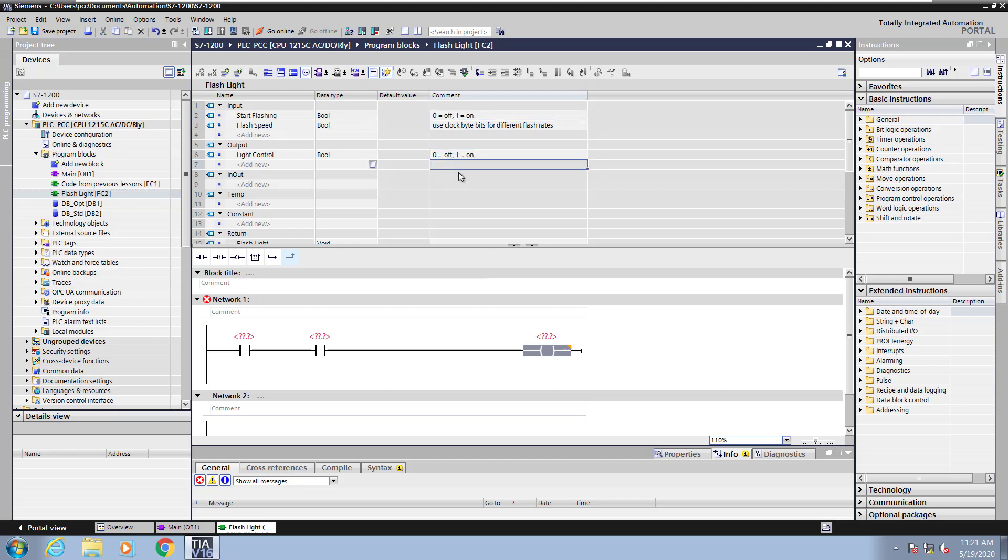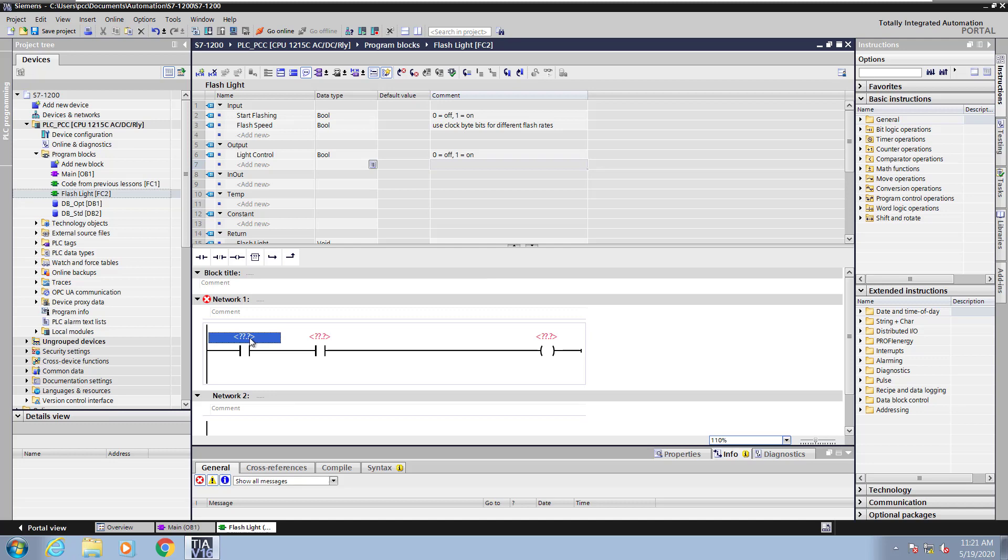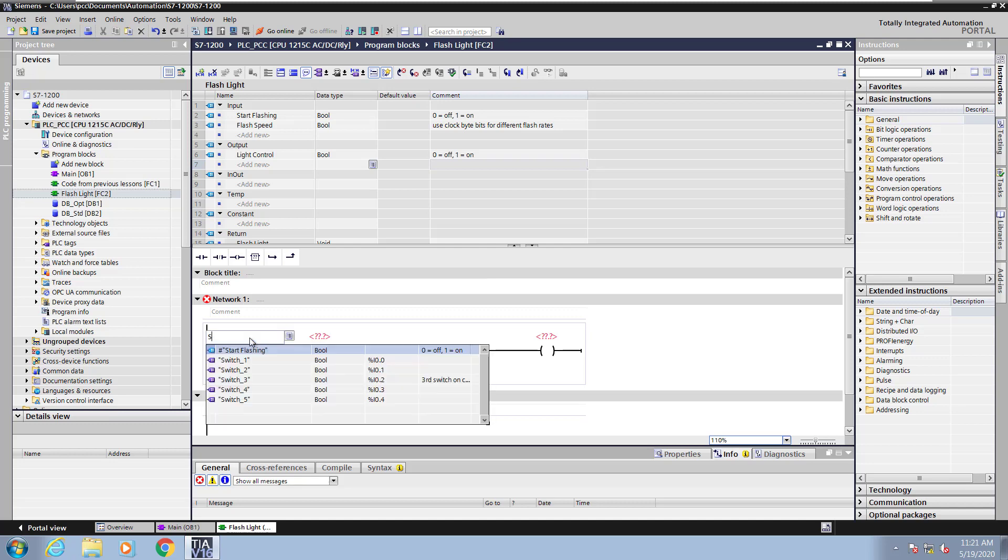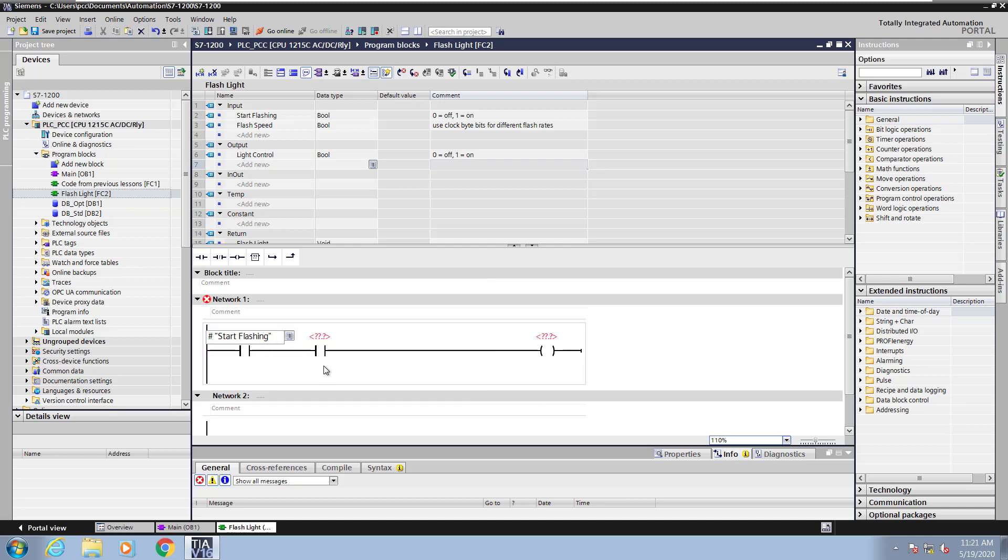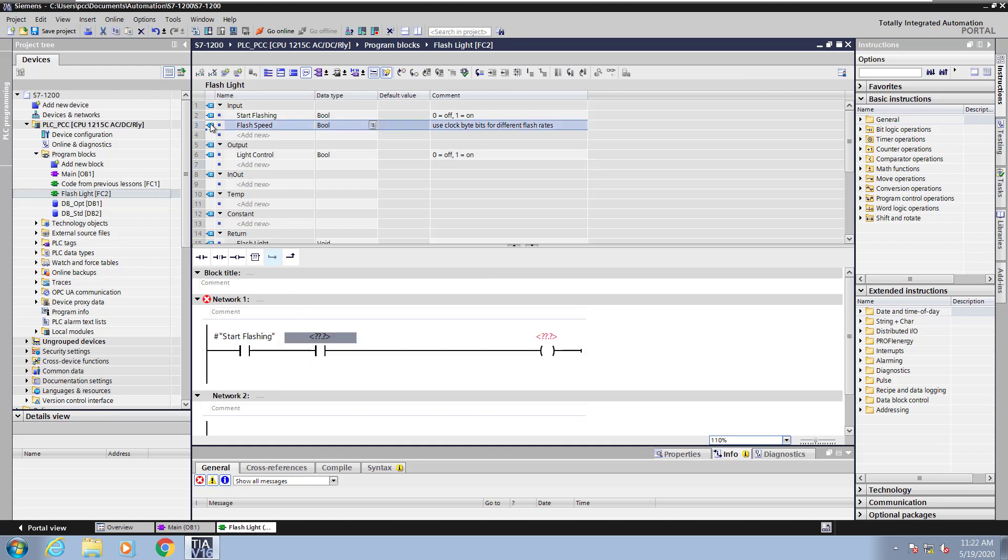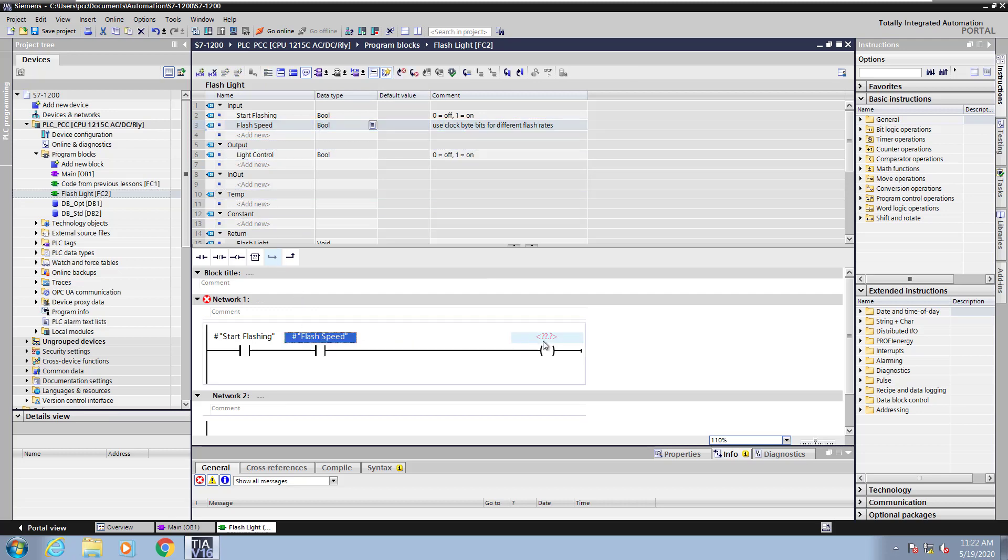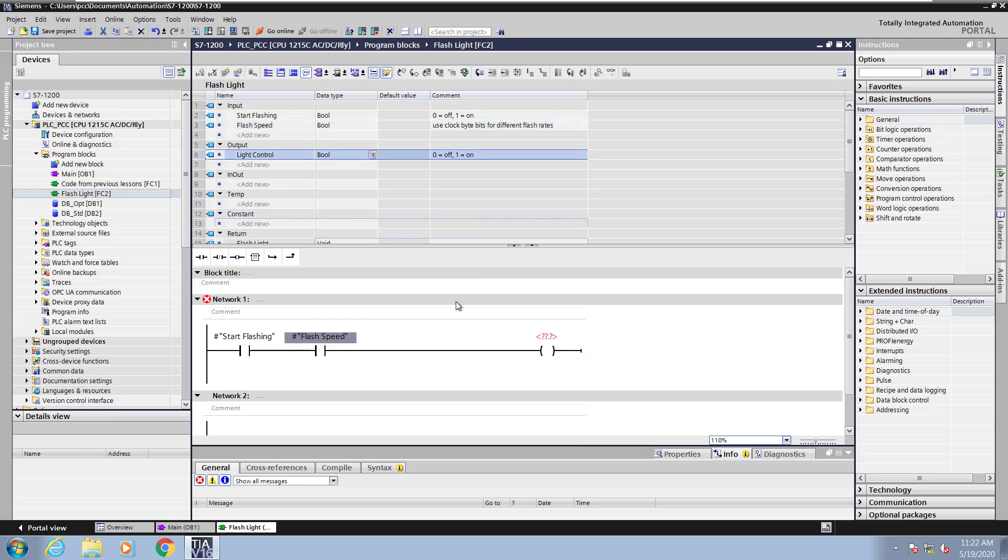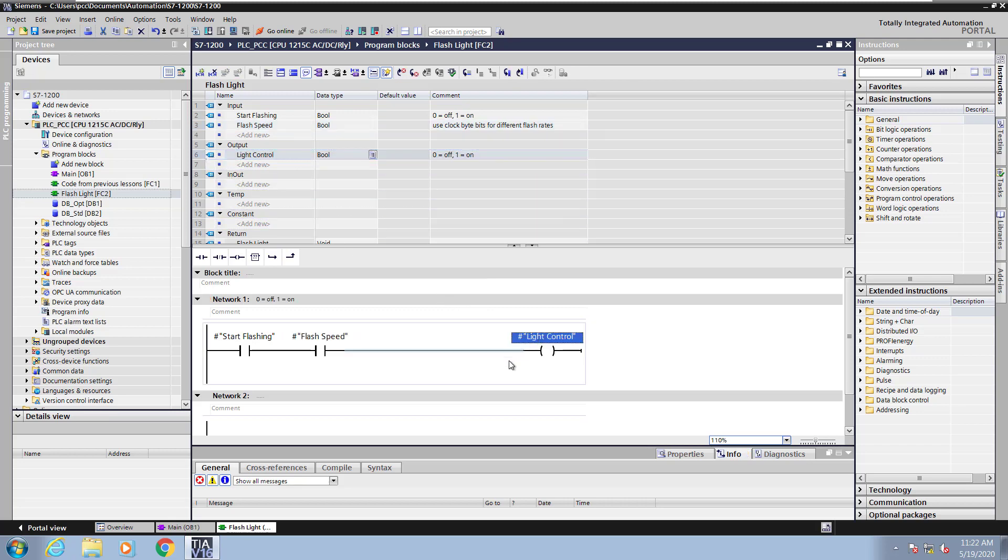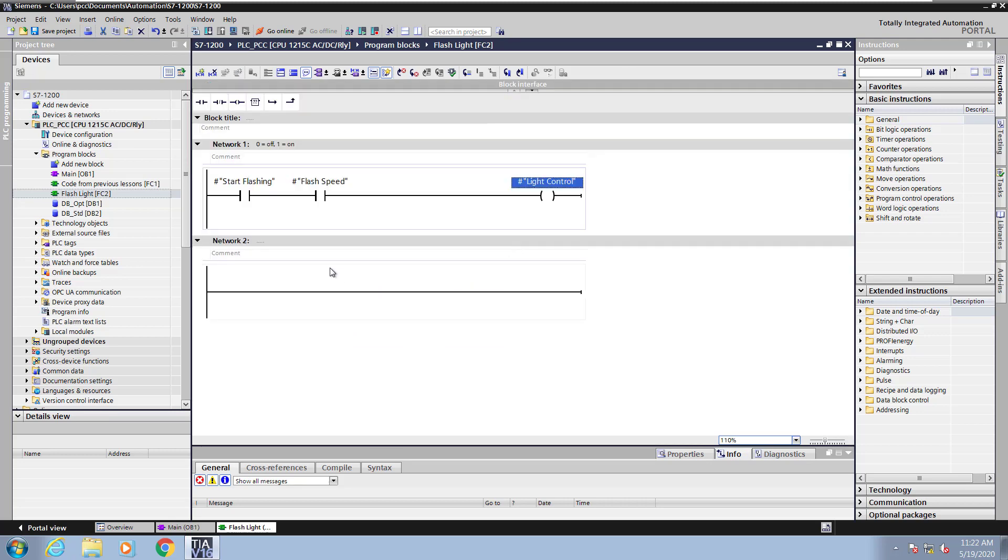To fill in the addresses for the ladder logic, I can just start typing the first few letters of a tag or local symbol. So when I type in the letter S, you can see that it gives me all of my global tags as well as the local symbol start flashing. I can also use the drag and drop method. So if I drag the flash speed from the input area down to my logic, you can see that come in. I can also drag the light control. Local symbols will have a pound sign in front of them, so you know that those symbols are coming from the local interface area.